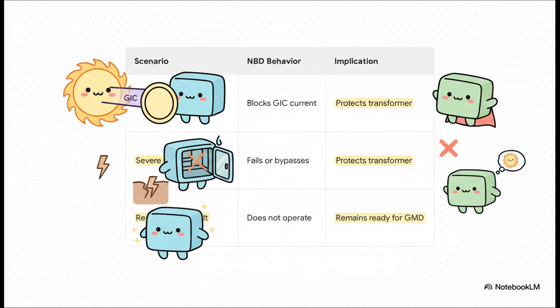Scenario 1, a solar storm: the NBD does its job, it blocks the current, and boom, the transformer is protected. Scenario 2, a really severe ground fault: the NBD knows it's out of its league, so it fails on purpose and gets out of the way. And guess what? The transformer is protected.